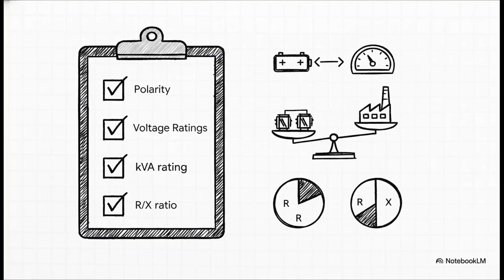First, like we said, polarity has to be the same, no question. Second, their voltage ratings need to be pretty much identical. If they're not, you'll get this big, useless current circulating between the two transformers, wasting energy. Third, and this is kind of a no-brainer, their combined power rating, the kVA, has to be more than the load you're trying to power.